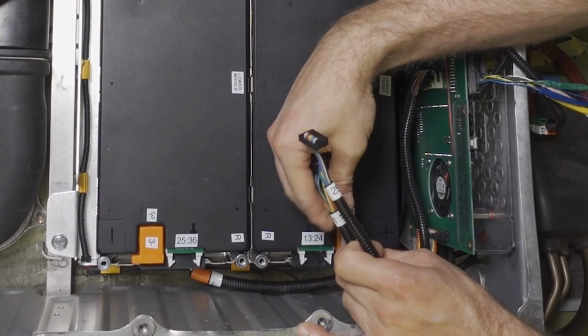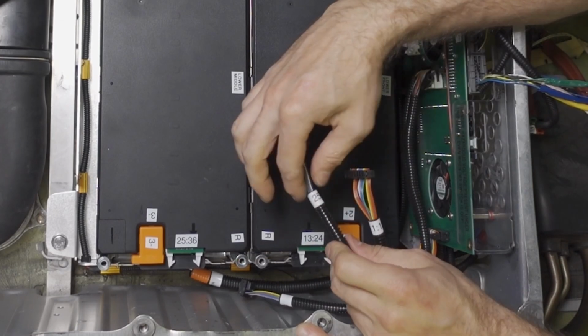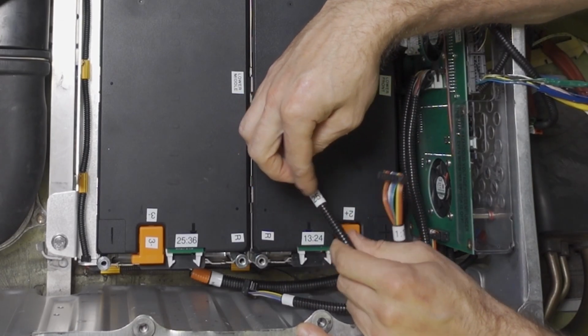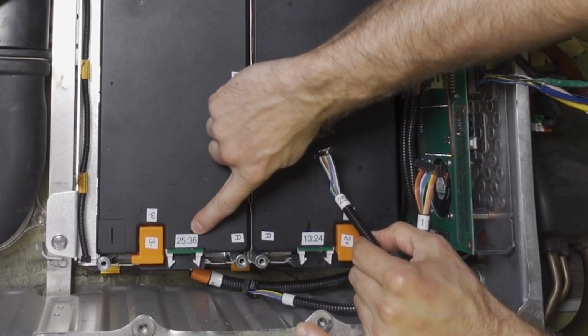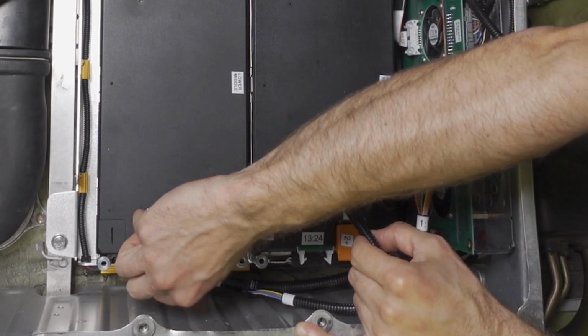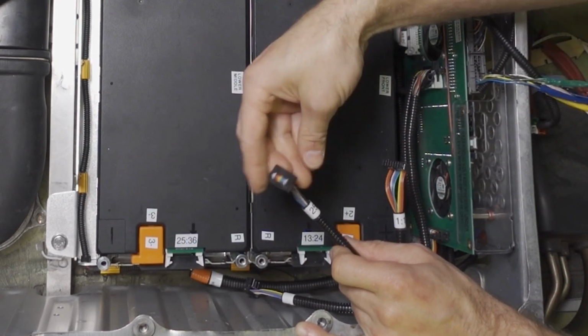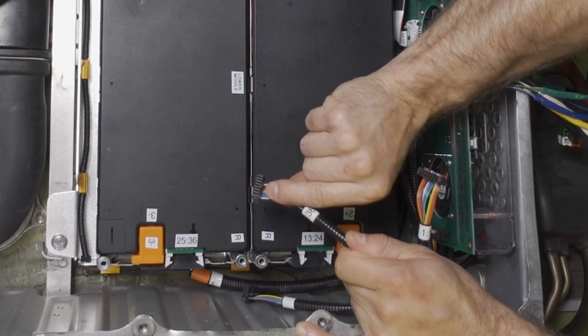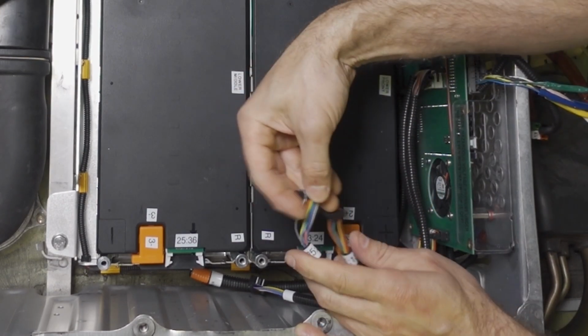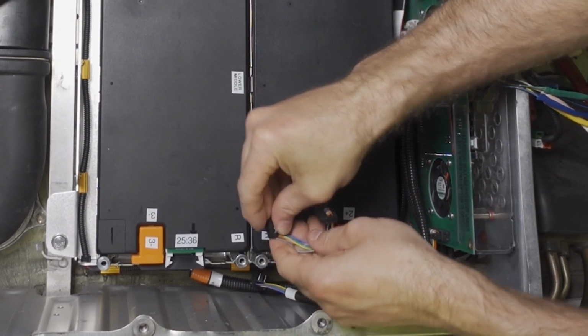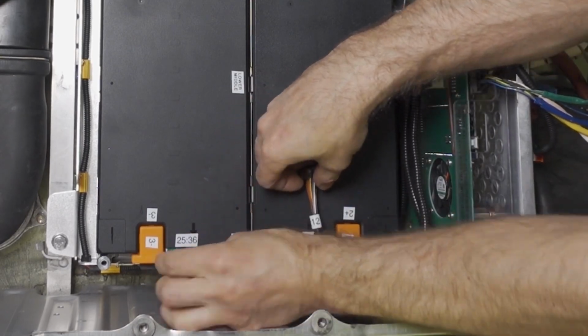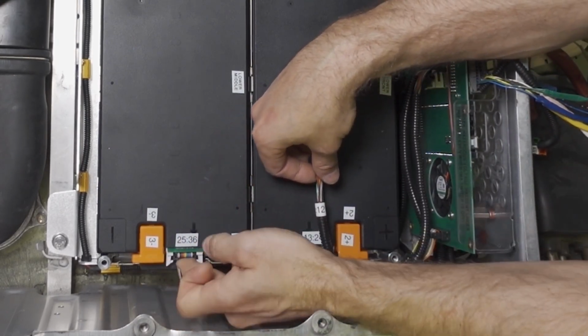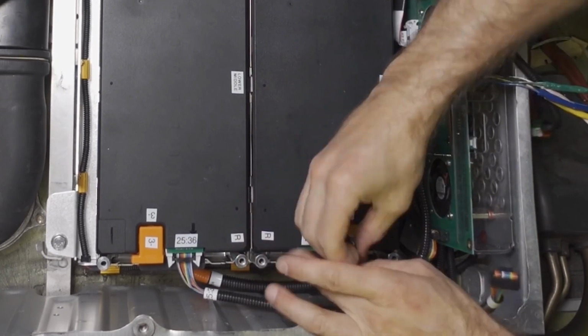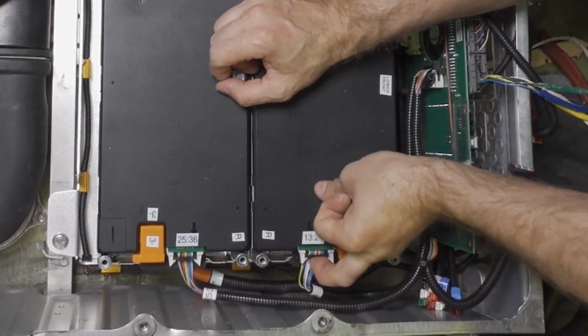And now on this part, we need to be really careful that we plug these in correctly, because if you do this wrong, you're gonna damage this circuit board. This one is marked 25 through 36. We're gonna match it up with the 25 through 36 here. So we'll go ahead and just open these up slightly. And we're gonna take this, the tab that's on this points down, which means the ribbon cable needs to have a bend on it here so that it will plug in. We're gonna repeat the same thing for the one that's marked 13 through 24.